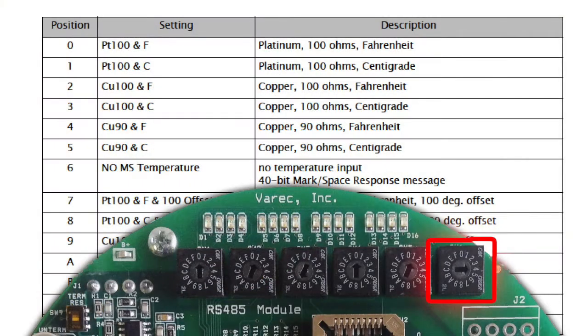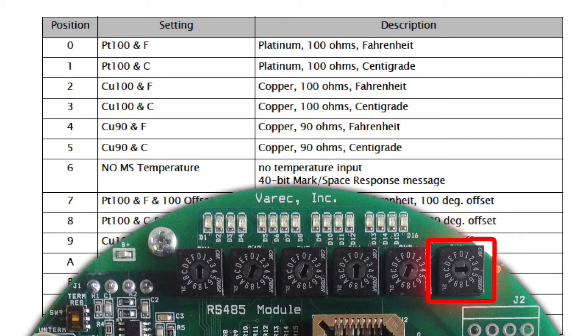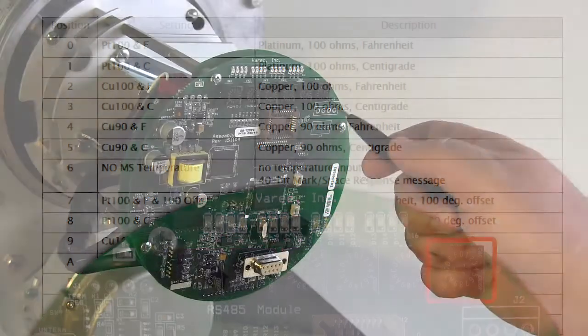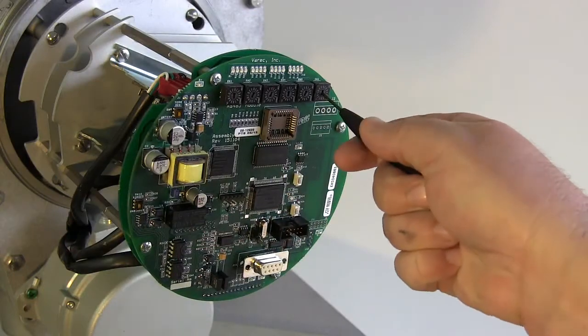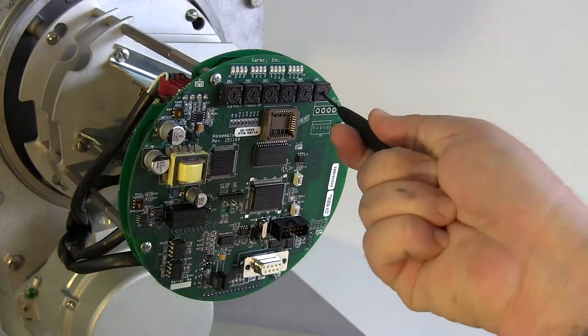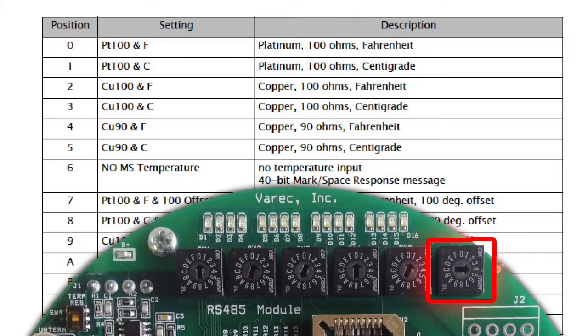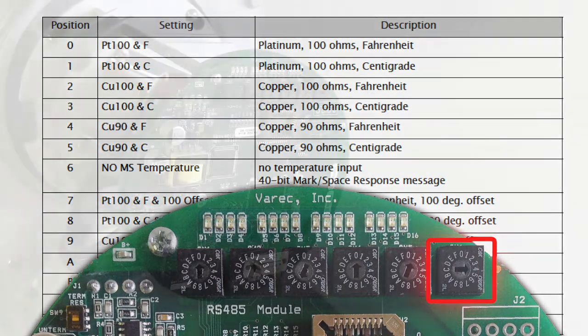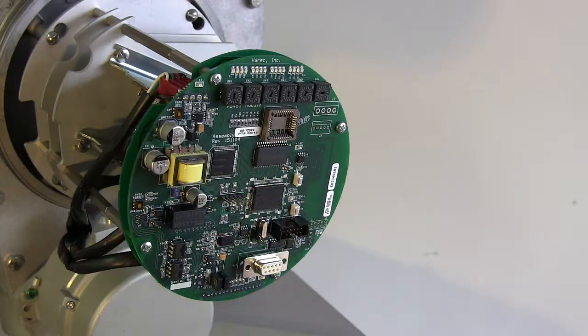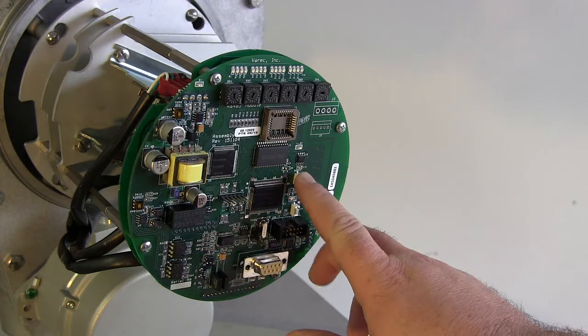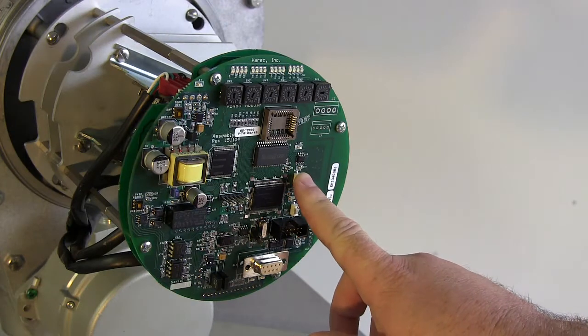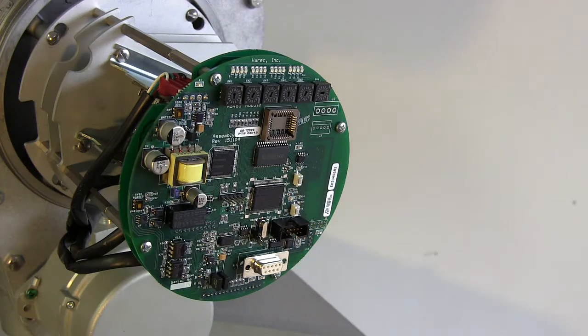To accurately obtain readings from a spot temperature RTD, the new encoder must be set to match the RTD type and temperature format. Switch SW6 configures this. We are setting this to match a copper-90 Fahrenheit RTD without an offset, position 4. But again, check your required setting in the manual. And once again, press SW7 to save the change.